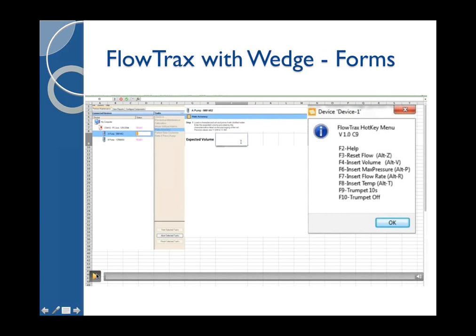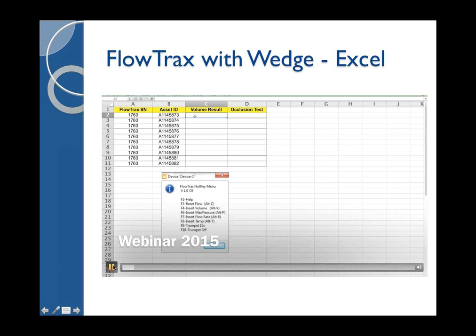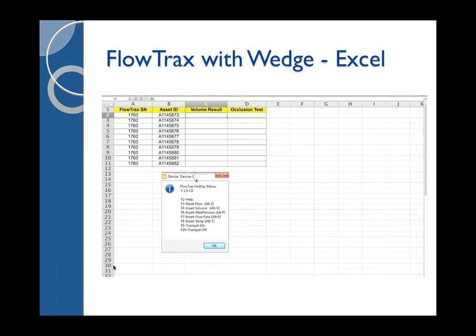So this is an example of that Wedge program in use. And what we're showing here is an Excel file that I created. It's got the Trax serial number, the asset ID of the IV pump under test. And what you'll see here is I'm clicking on a cell in Excel, and then I'm hitting an F key to ask Trax for the volume result. Also, you can do that for occlusion testing. You can ask Trax by hitting F6 to send the data over to Excel for the occlusion pressure. So I'm going to show just 2 or 3 examples of this on the screen.